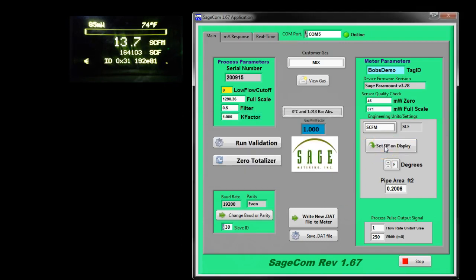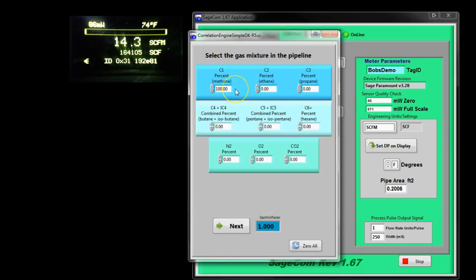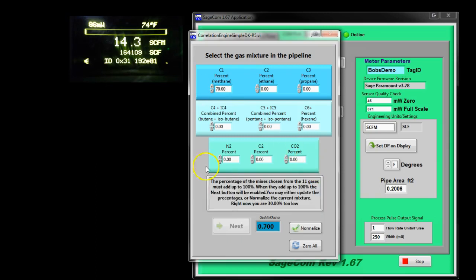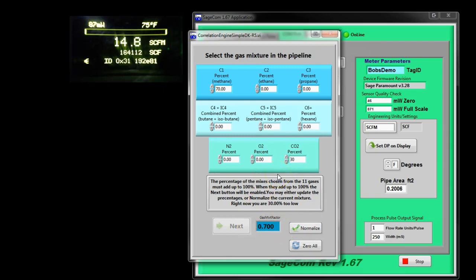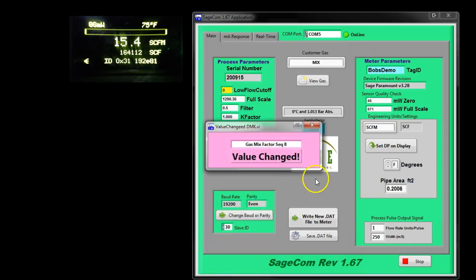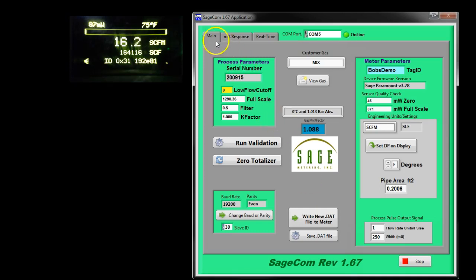So folks, are you seeing how easy it is to just enter fields? You can even change the gas mix. This particular meter, as I click view gas, was calibrated for 100% methane, which is always used for natural gas. And suppose the application is really 70% methane and 30% CO2. Well, I'll put in 70 up here. And if I forget to do CO2, it warns you that you have not done 100%. You can either normalize or better yet take it to 100% yourself. Press the return key. Hit next. And you'll see the K factor has changed. Because essentially what's happened, your meter now is a new meter. You haven't had to send it back. And now it's a 70, 30. And the gas mix factor lets you know that you've changed something. Well, that's pretty much it for the examples I want to show you on what we call the main.